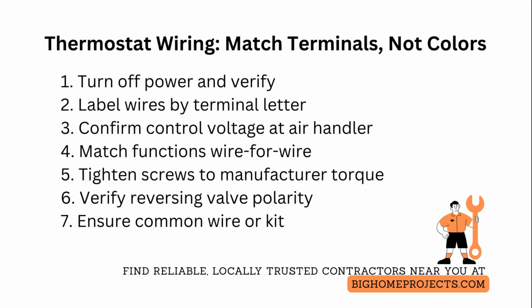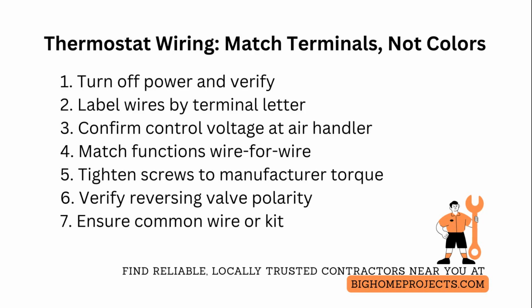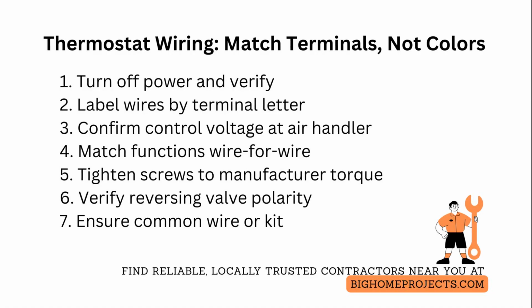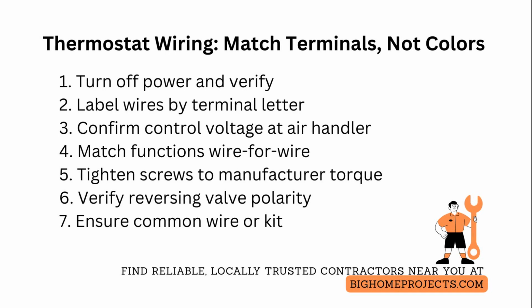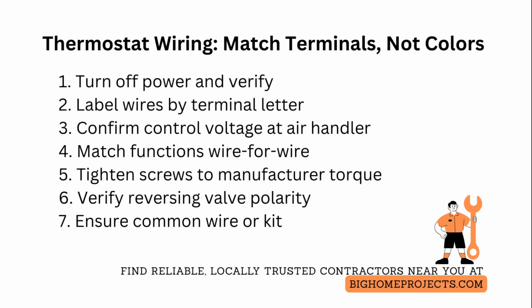If terminals at the air handler are push-in or screw type, replicate the exact terminal-to-terminal connection rather than relying on conductor color. If the control board has printed labels, match to those letters and tighten screws to manufacturer torque recommendations to avoid intermittent contact. For heat pump setups, confirm reversing valve polarity and auxiliary staging with a meter and reference the outdoor unit wiring diagram. Miswired reversing valves cause the system to run opposite mode.